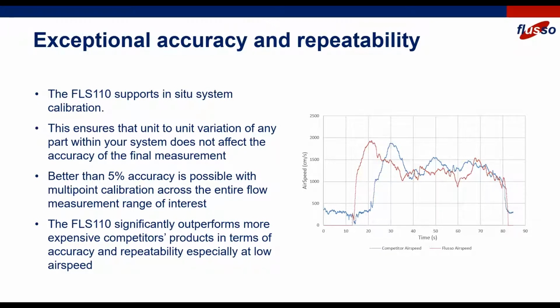We find that better than 5% accuracy is possible when you use multi-point calibration across the range of interest. And the FLS110 significantly outperforms more expensive competitor products in terms of accuracy and repeatability, particularly at low airspeed, as shown in the graph on the right.